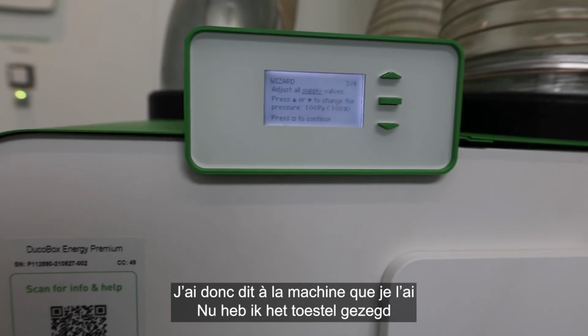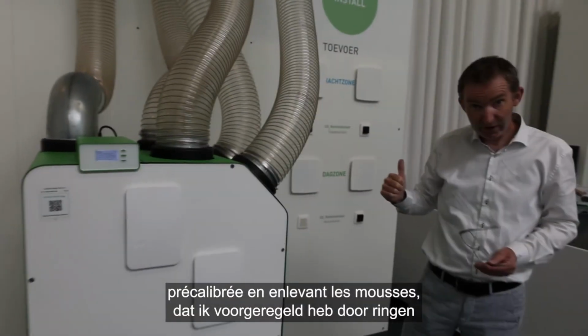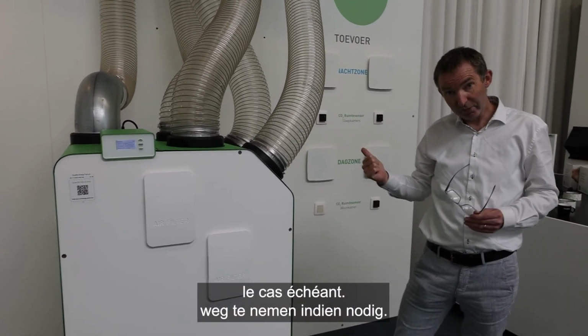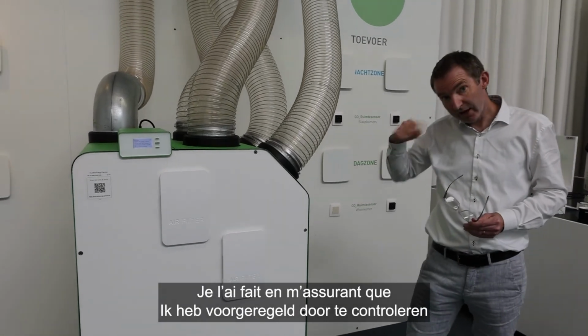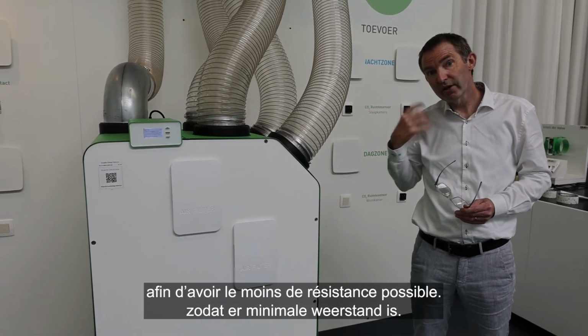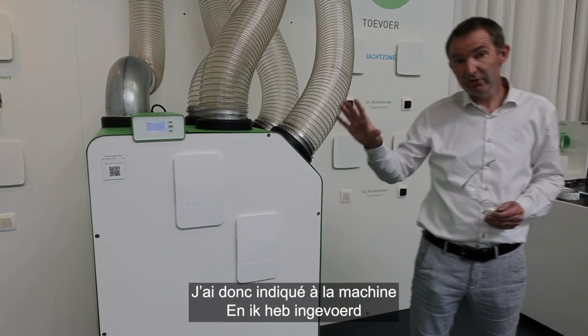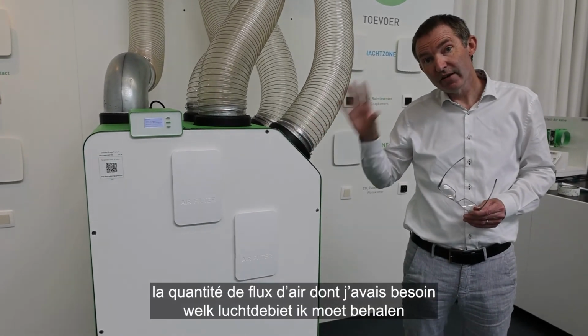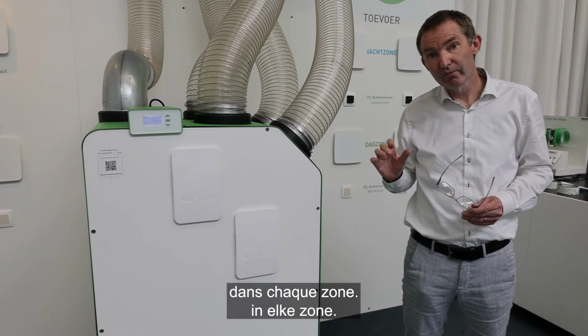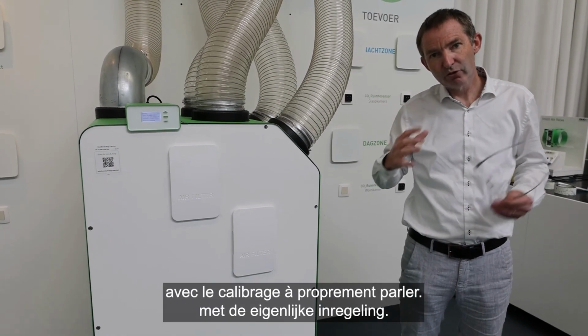And there you go. So now I've told the machine, I've pre-calibrated by taking out mousses if applicable. I've pre-calibrated by making sure the vents are fully open so that there's least resistance. And I've told the machine how much airflow I need in every single zone. Now I can go further with the actual calibration.